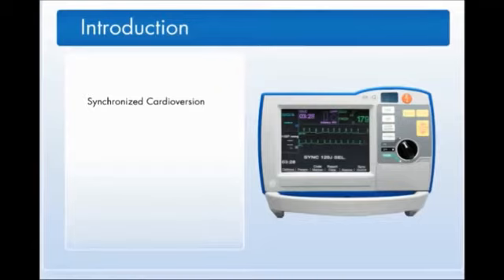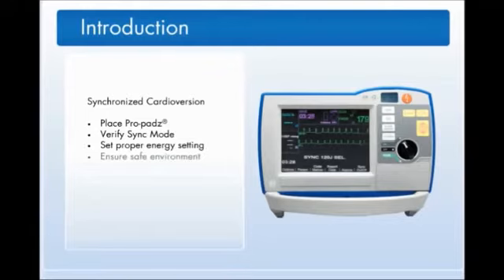In this module, you will learn how to properly place Pro-padz on a patient, how to verify the device is in sync mode, how to set the proper energy setting, how to ensure a safe environment when performing defibrillation, and how to use the R series to deliver a series of synchronized defibrillation shocks. It is important to note that only skilled personnel trained in cardioversion procedures should perform synchronized cardioversion.